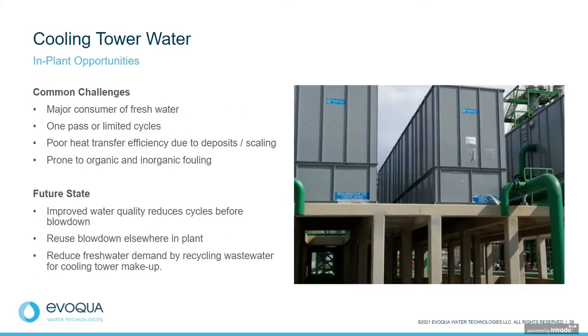The cooling tower is a major consumer of water. It's also pretty flexible, being in the middle. You can reuse the cooling tower blowdown elsewhere in the plant. I've heard of it being treated and then used as first and second rinse CIP. You can also use wastewater as feed for the cooling tower system, which is what I meant to say on the boiler slide. So cycle it up, put in a filtration system, get more uses of that cooling tower water before you blow it down, or use that water elsewhere in your plant.